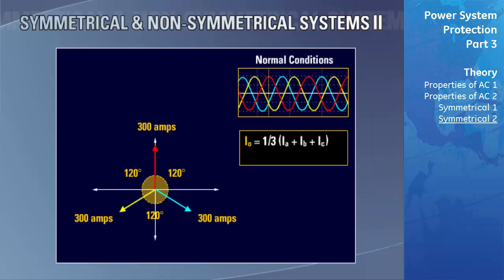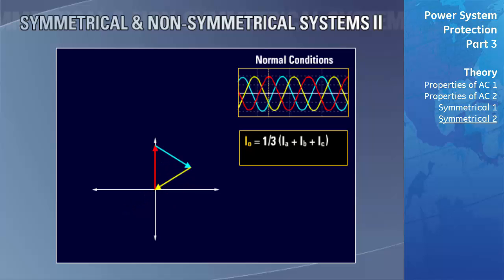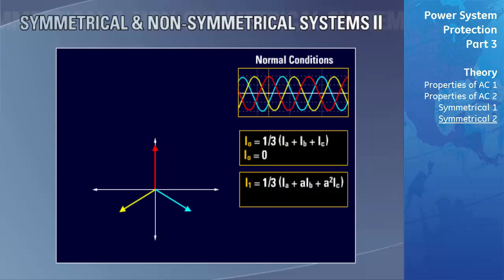Zero sequence uses the formula (Ia + Ib + Ic) / 3. By vector addition of all three phasors, they cancel each other out, resulting in a zero sequence of zero amps. The positive sequence uses the formula (Ia + A·Ib + A²·Ic) / 3. Phase B has an A operator applied, rotating the vector 120 degrees counterclockwise, lining it up with phase A. Phase C has an A-squared operator, rotating the phasor 240 degrees, also aligning it with phase A.